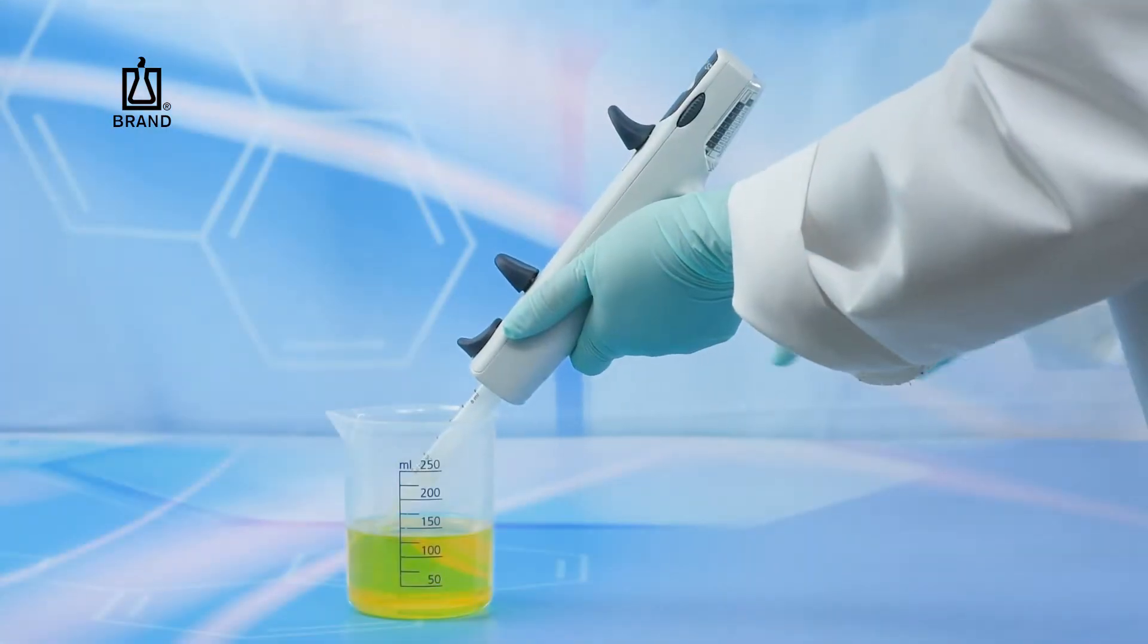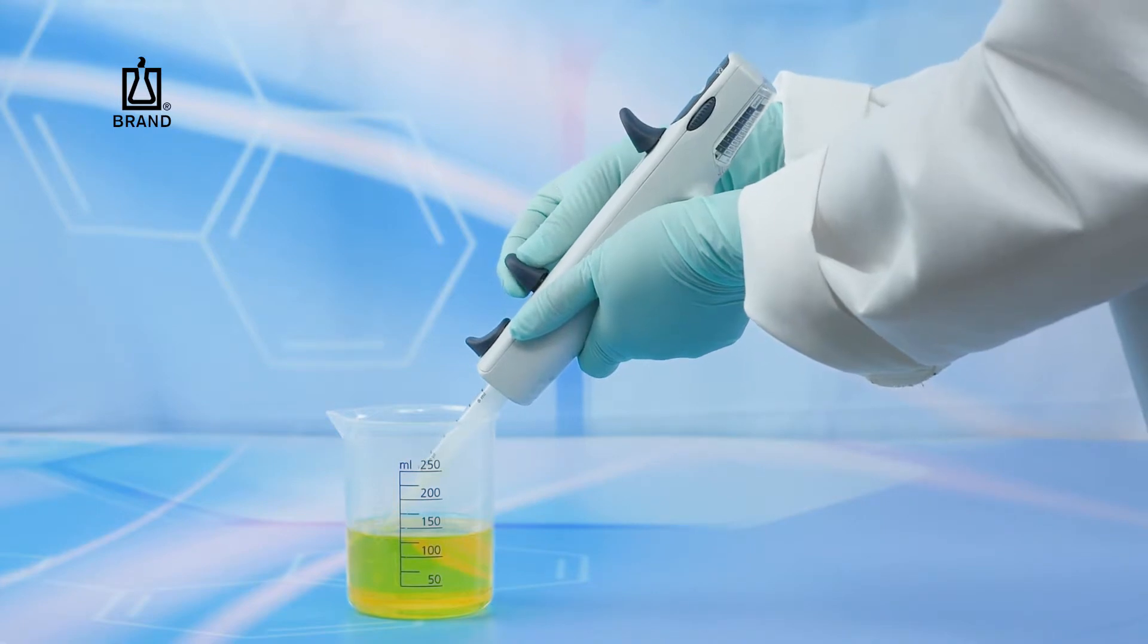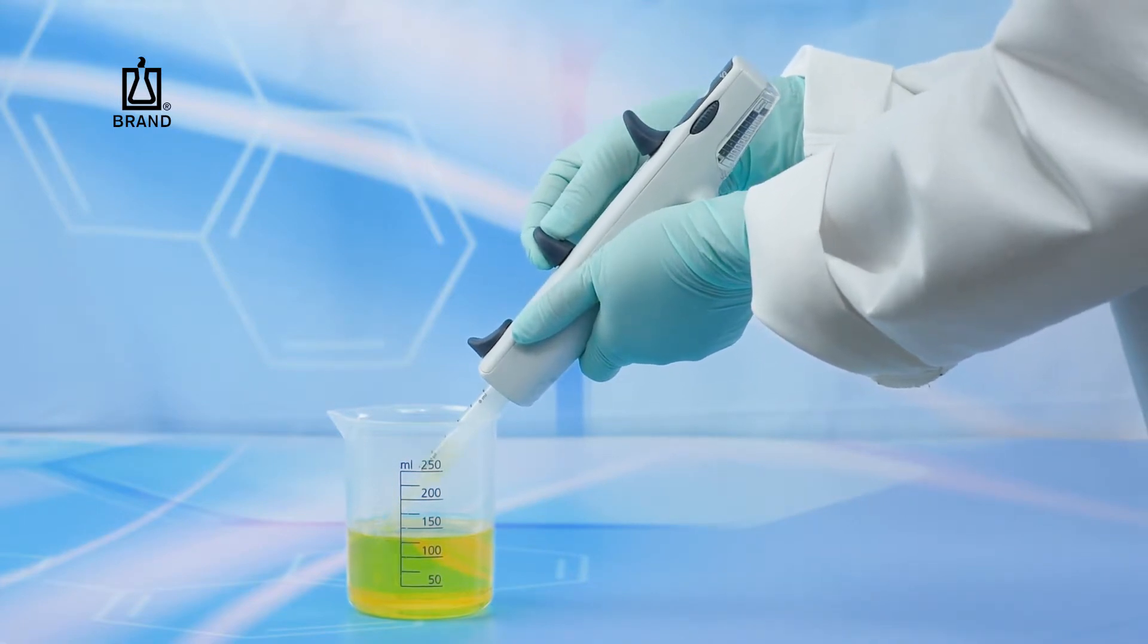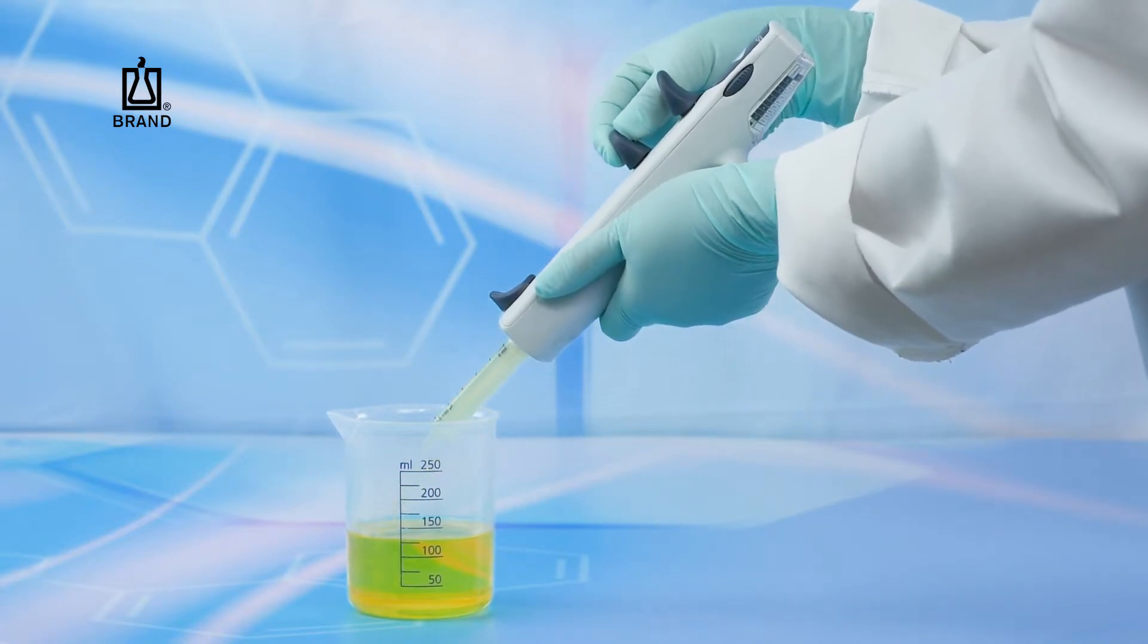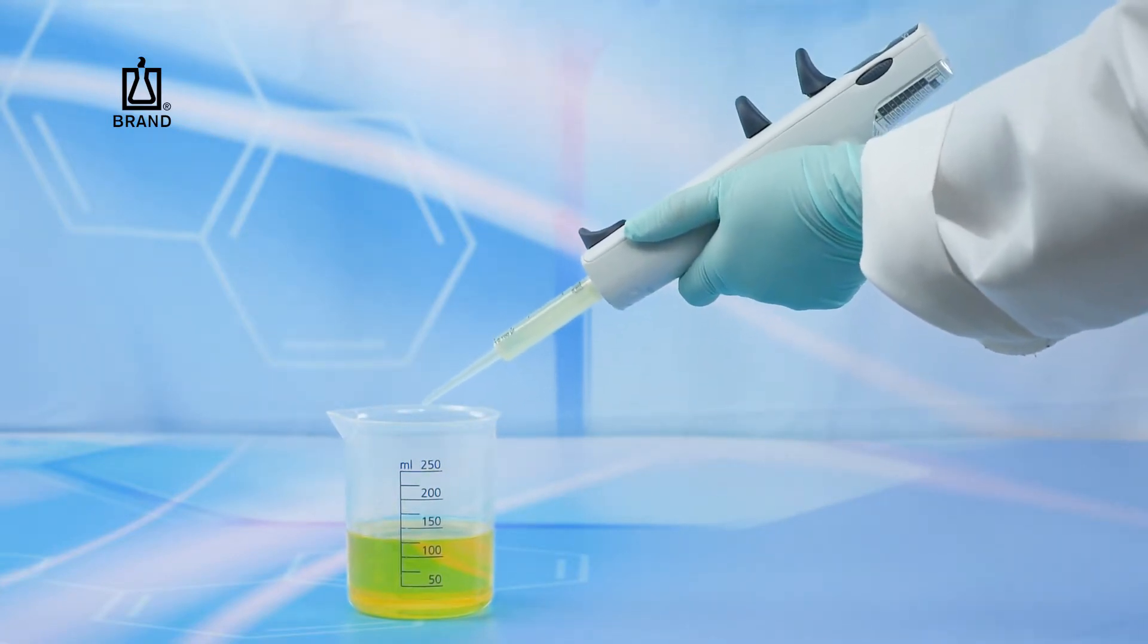To aspirate liquid, make sure the piston is in the lower position. Insert the end of the PD tip 3 to 10 millimeters into the liquid to be dispensed and pull back slowly on the locking filling lever to draw the liquid into the PD tip.